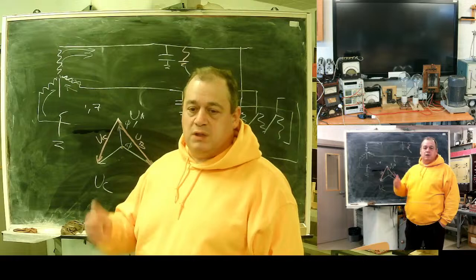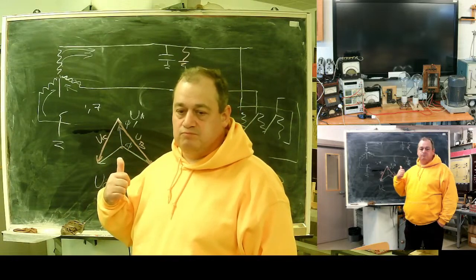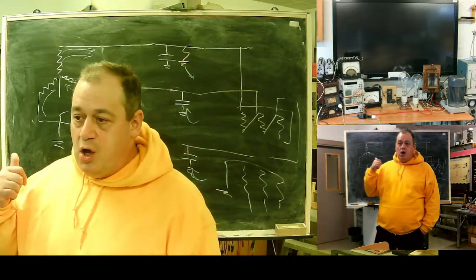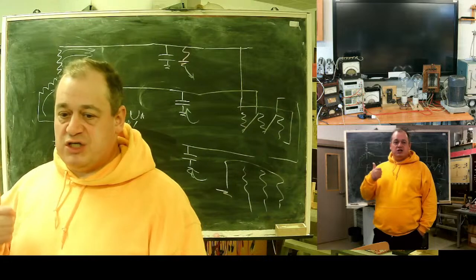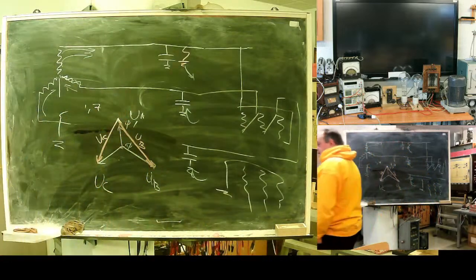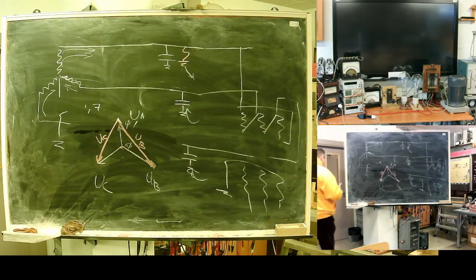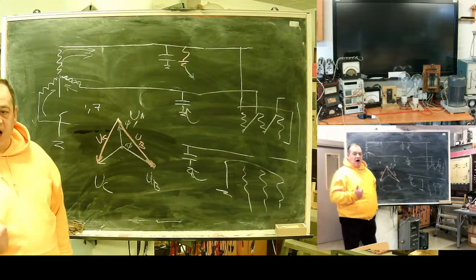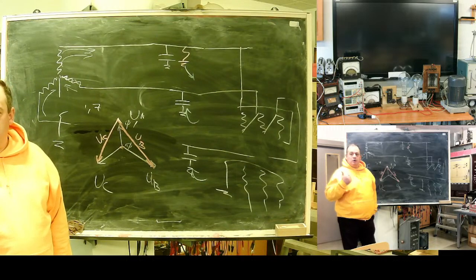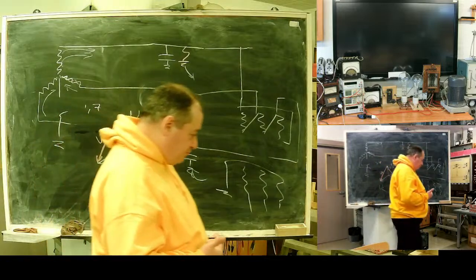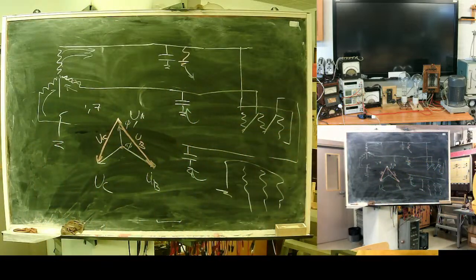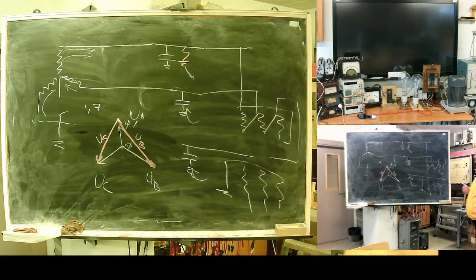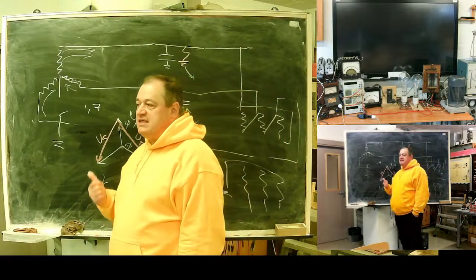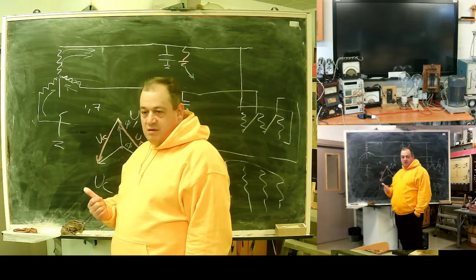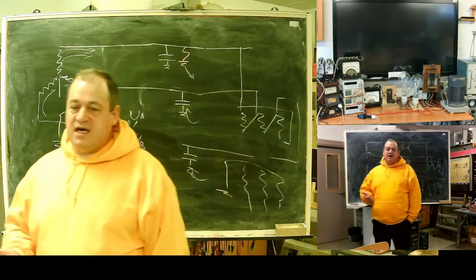Another problem is that this fault may involve a human. Earth fault current is dangerous to humans. So in populated areas now, a risk management strategy asks us to clear this fault, to disconnect the line, because it's dangerous to living beings. So protection is needed in inhabited areas.